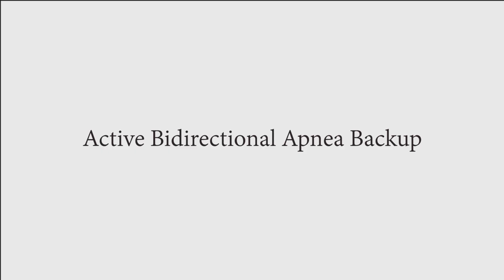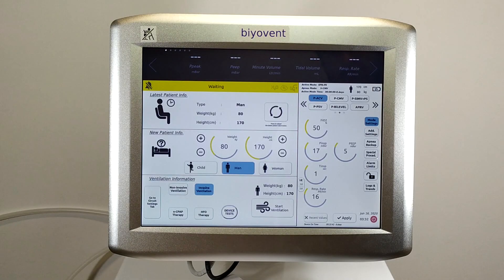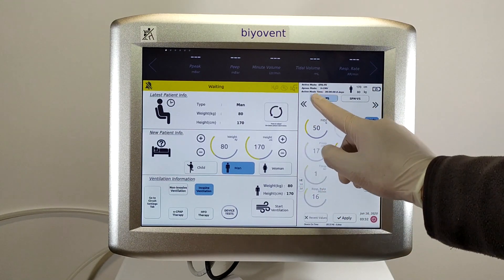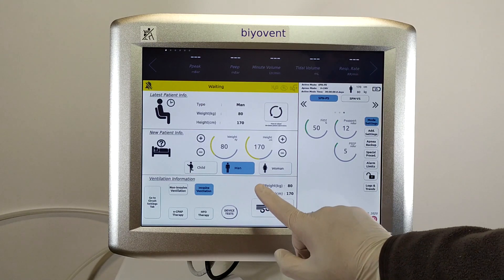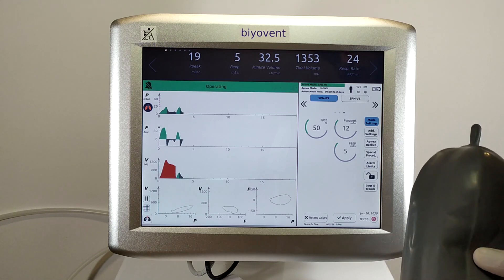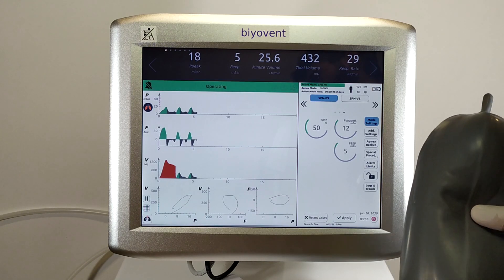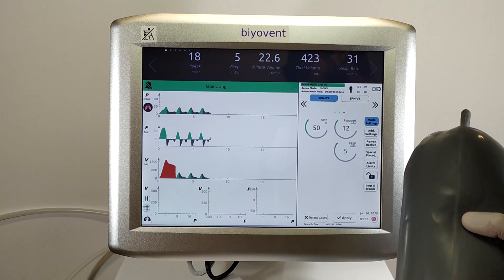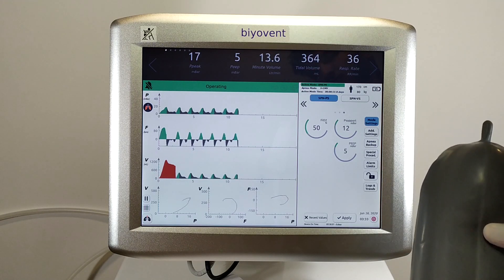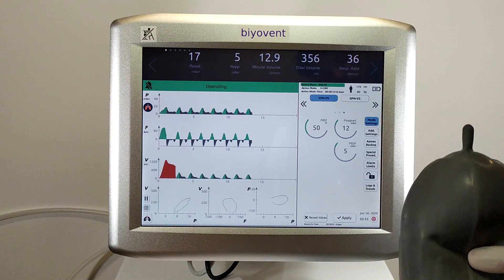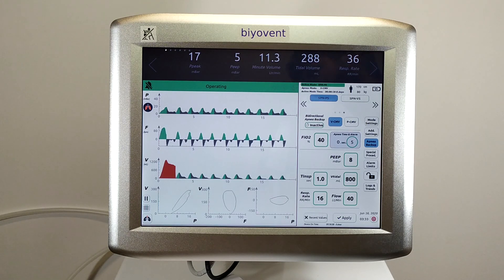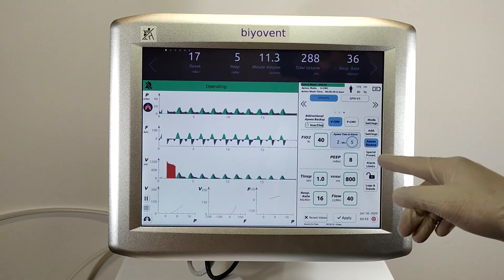Now let's simulate with the active bidirectional feature. After all settings, let's choose pressure control spontaneous mode from the mode settings, then start ventilation. I simulate the patient's breathing with my hand. As you can see, with the patient triggering, the BioVent works normally. When you touch the apnea backup button, you can see the apnea settings which you have already set.